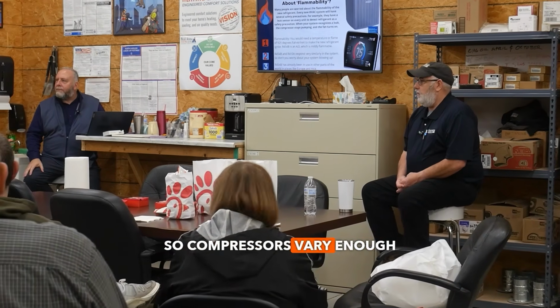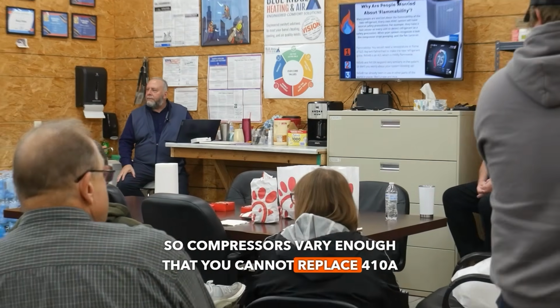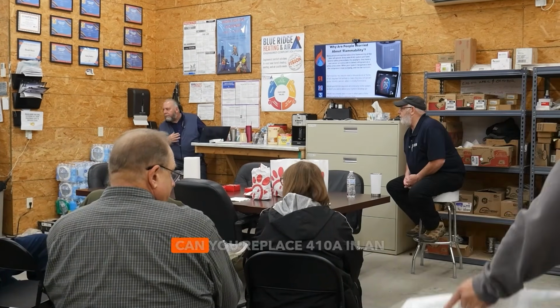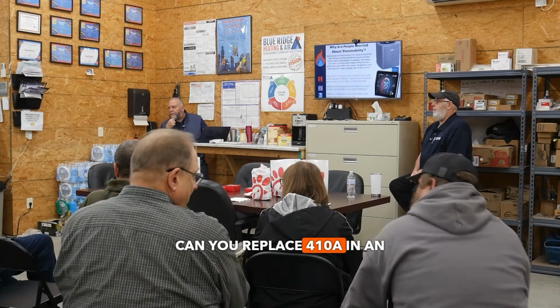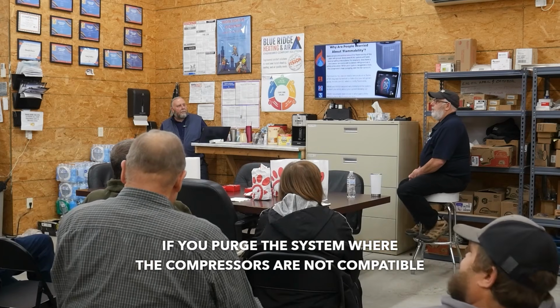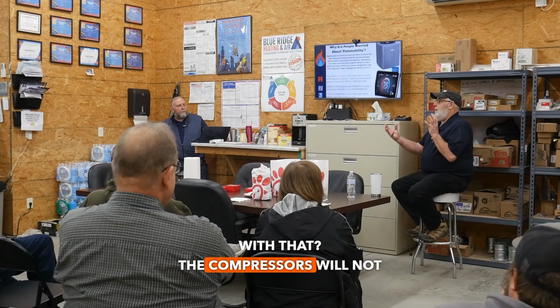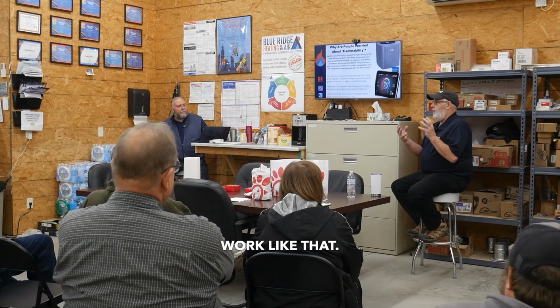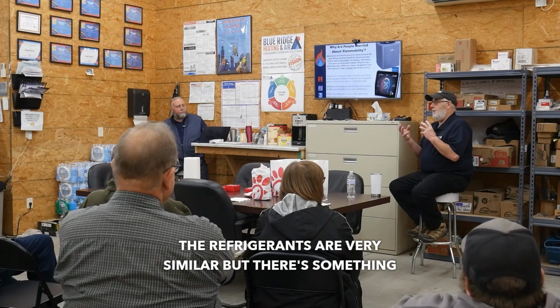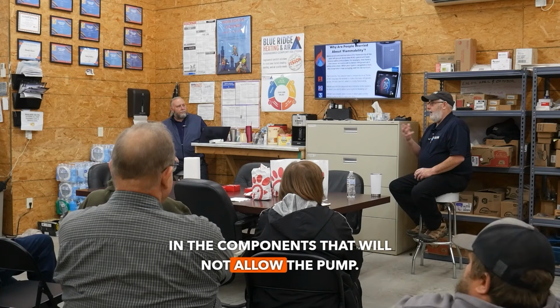So the pressures vary enough that you cannot replace 410A with the new refrigerant? Say that again, please. In other words, can you replace 410A in an existing unit with a new refrigerant if you purge the system, or are the pressures not compatible with that? No, sir. The compressors will not work like that. They're designed for the 454B or they're designed for the 410A. The refrigerants are very similar, but there's something in the components that will not allow it to pump.